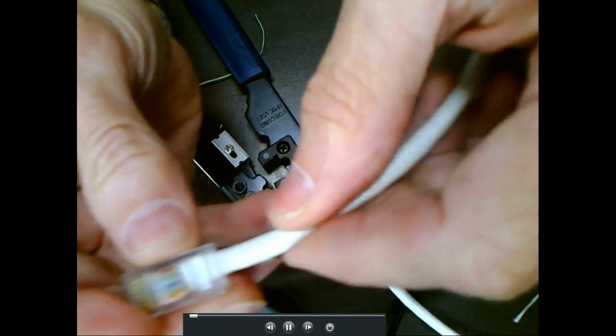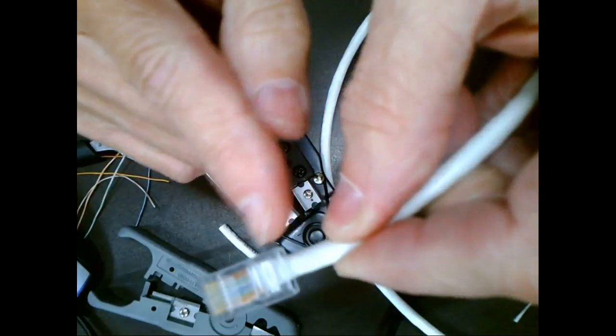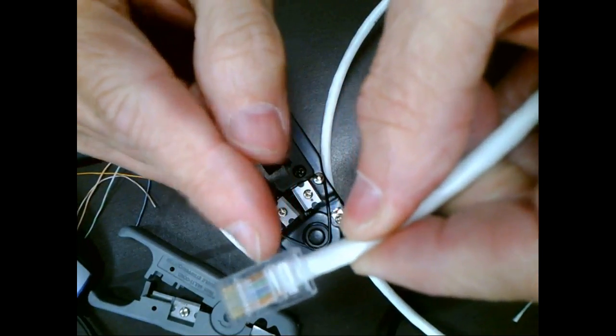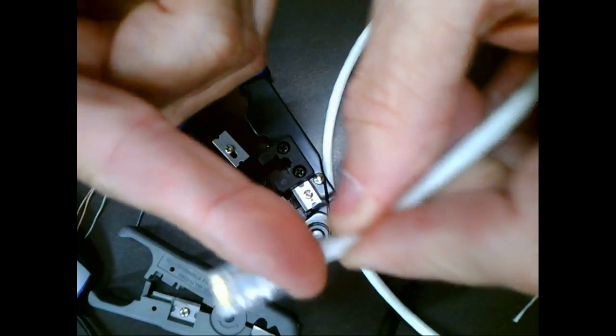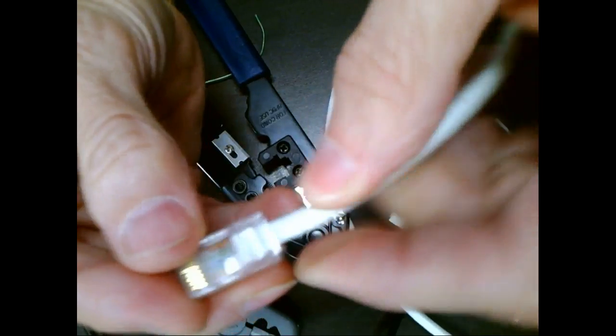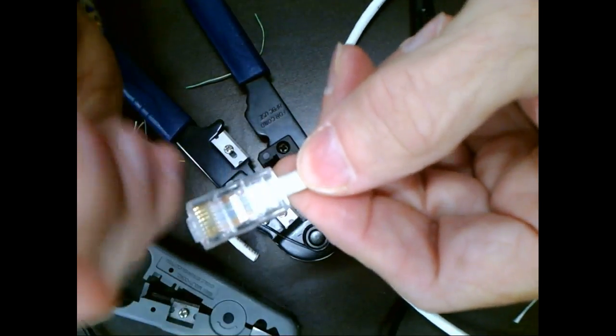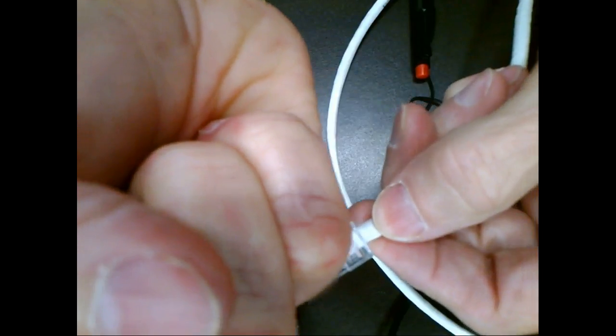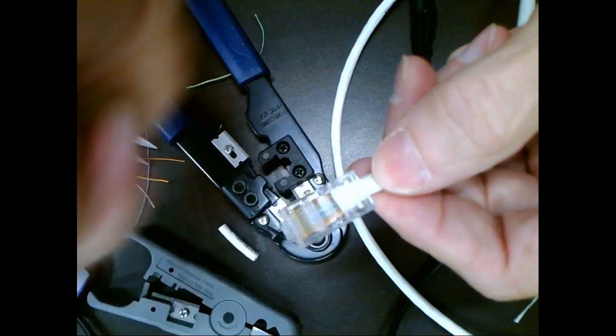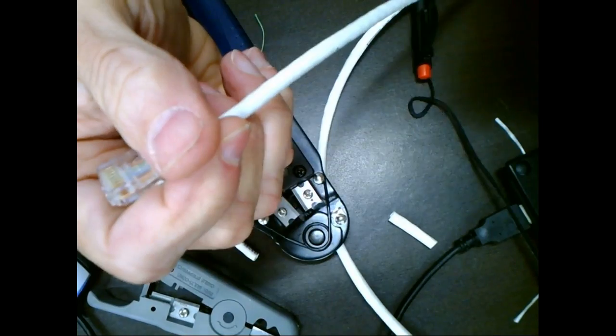You understand what I'm talking about, yes or no? So see how far my jacket goes up in here? You need to make sure it gets below this indentation right here. Because if you don't do that, then all the stress on the cable is on those crimps on your wire. Right? You understand that? And if somebody jerks on it, it'll just pull right out of it.